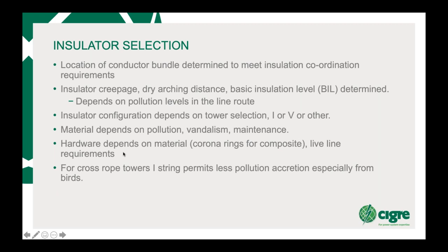For cross rope towers, the I string permits less pollution accretion, especially from birds. If you're using V strings, you find bird excretion can gather in the apex of the V, causing pollution on the string and then flashovers to the tower.